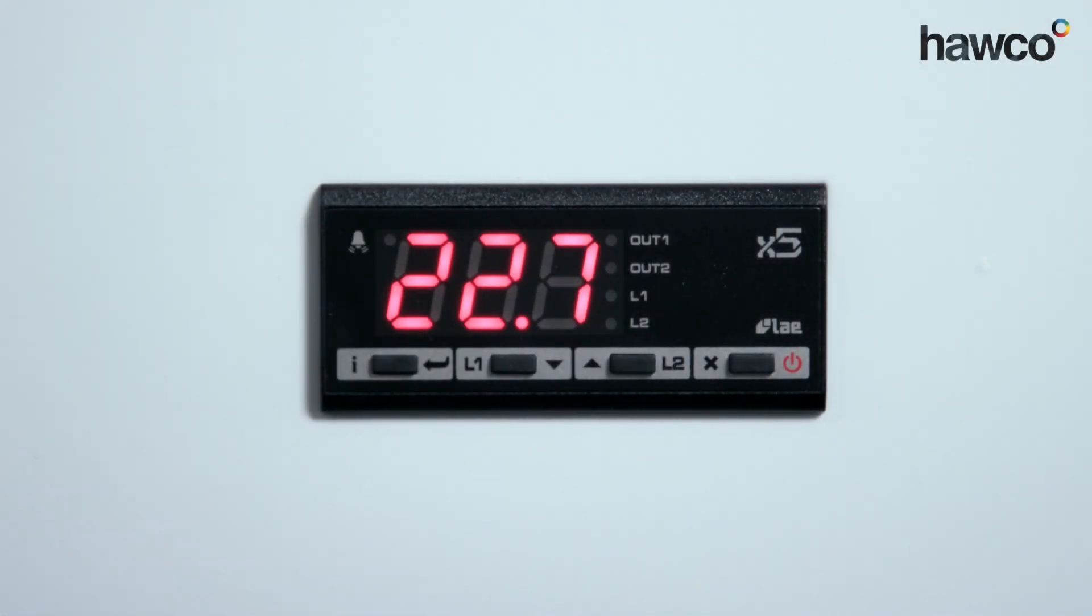Hello, we're talking about the AC1-5 from LAE. The great thing about this controller is that you can use both the relays, one can be for heating and one can be for cooling, so you can set up a dead band control. In this scenario, we're going to set up relay one to be our refrigerator, relay two to be our heater.